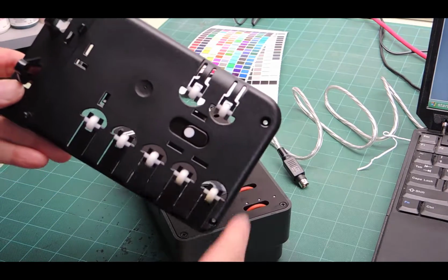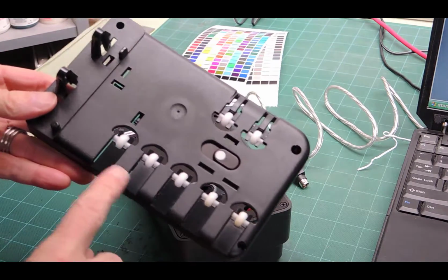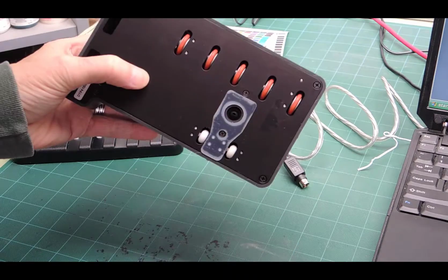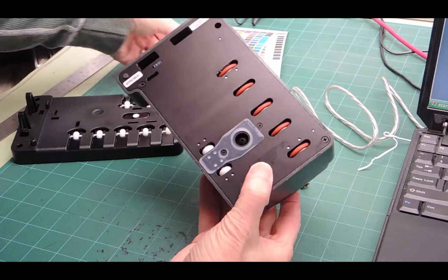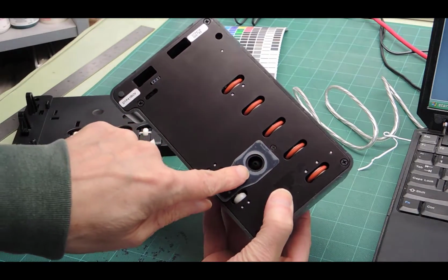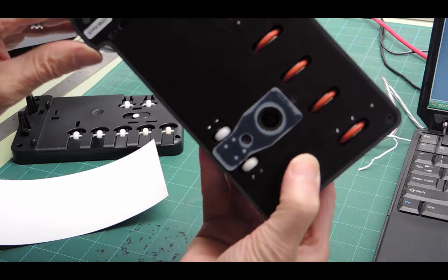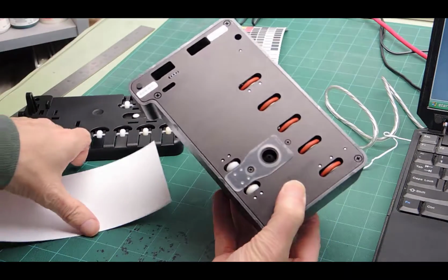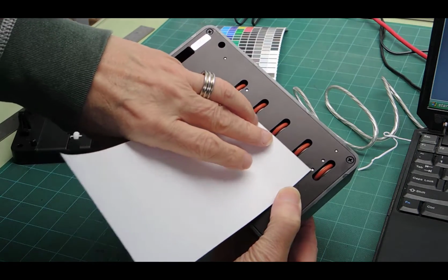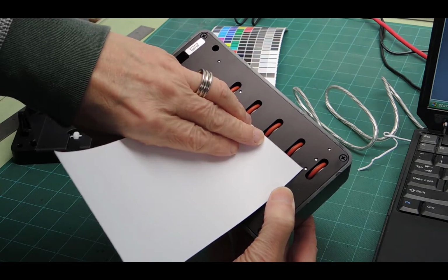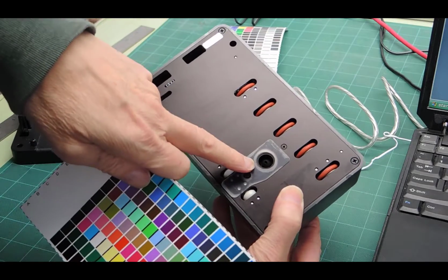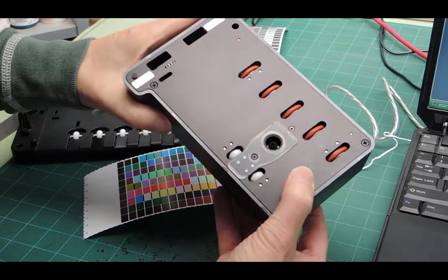You see, there's the front of the unit, I think, and this is the back of the unit, and this is what the unit looks like from the bottom. And what happens is that when we insert a strip, this is where the measuring head is. It's really small. I don't think you can see it all that well. It's a small head. So what we do is we rest the target sheet against those wheels, you see? And when we press the button, what happens is that the strip passes in front of the head and is measured that way. It's a beautiful instrument.